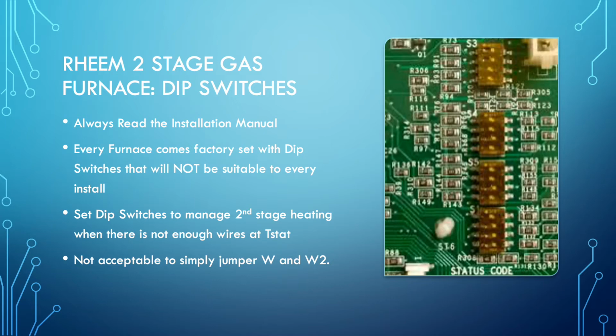But if you don't have that extra wire, there are dip switches in here that will allow the control board of the furnace to dictate when second stage heating should come on. Now, first stage heating, just so we understand, it's a reduction in the inducer draft motor rate of operation and the fire rate of the furnace. So everything kind of steps down with the gas valve, inducer draft motor. Now the blower will often step down to a lower fan speed also. When you go to second stage, everything amps up into a higher operational level, so it's getting more BTUs into the system.